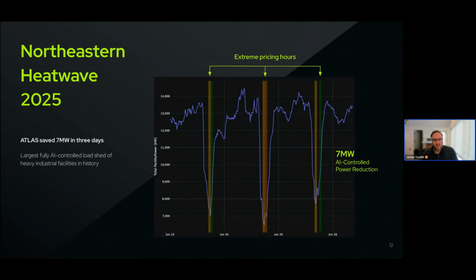This is where we saw Atlas was able to reduce our load automatically during these really high price spike events by about 7 megawatts on average across these 3 days. This was worth hundreds of thousands of dollars to Lineage in terms of savings generated. It's the largest fully AI controlled load shed in any heavy industrial setting, as far as we know. If anybody on the call knows of a different one or a bigger one, let us know.